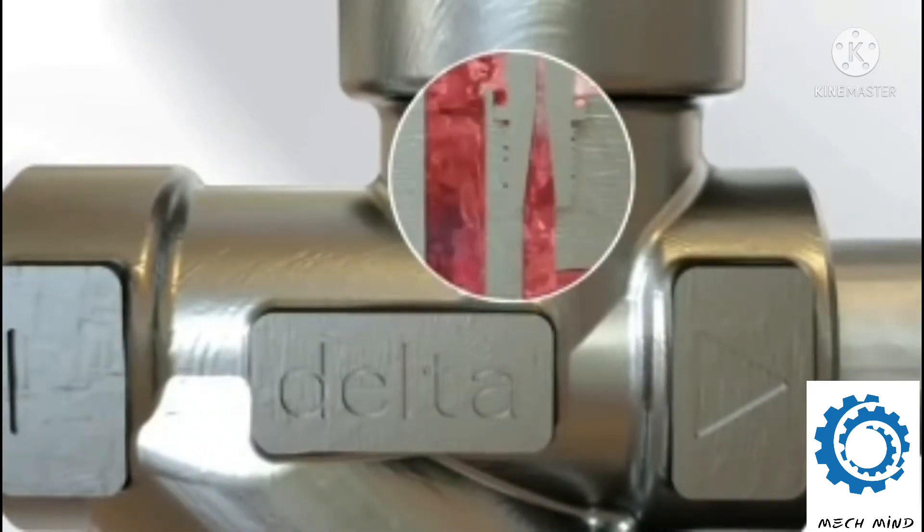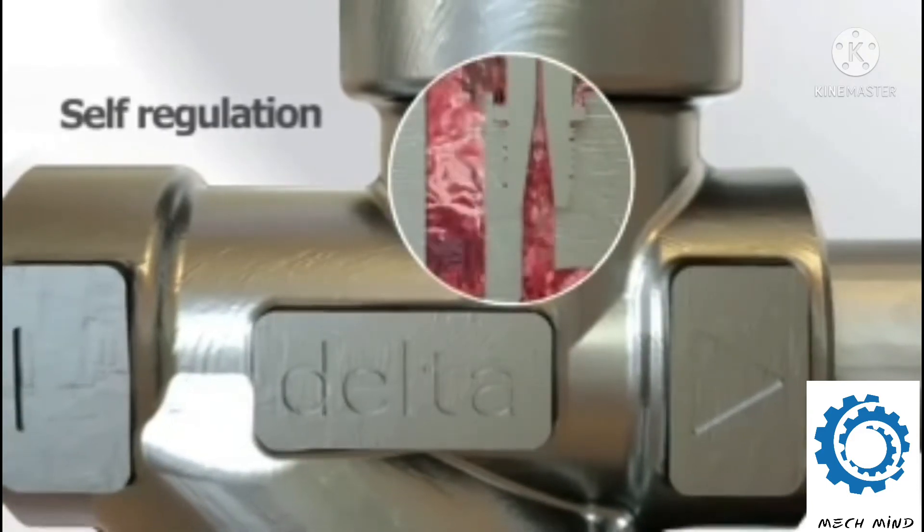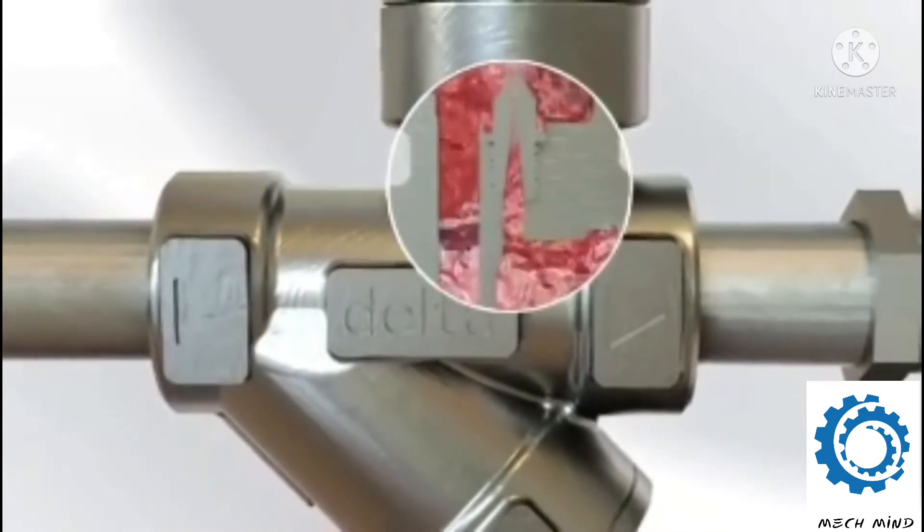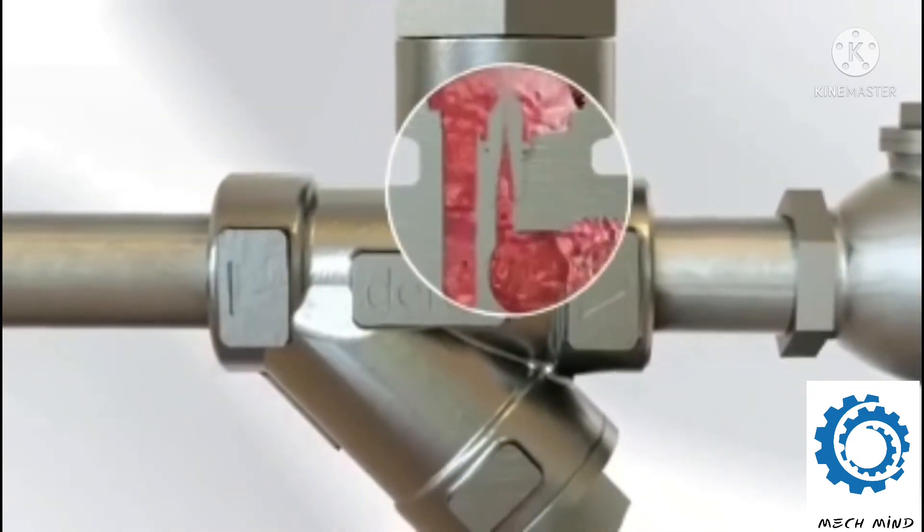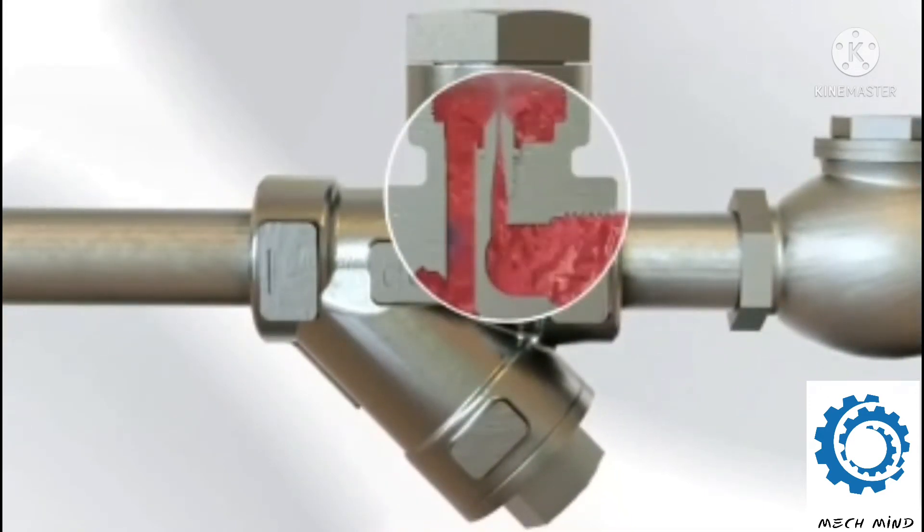This varying of back pressure at the mouth of the venturi allows the delta steam trap to self-regulate the condensate flow as the condensate load changes. As the pressure or load in the steam system rises or falls, the back pressure that is constantly changing at the mouth of the venturi also rises or falls.